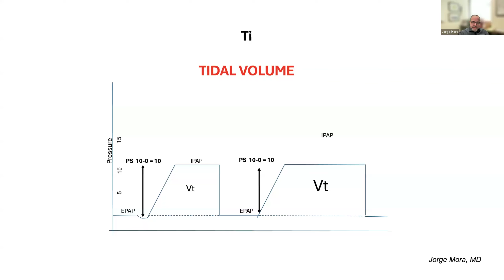Most devices right now, especially ventilators, but it's true for all respiratory assist devices, bilevel PAPs from ResMed, which is probably the most common used component. It's true also for Luna, React Health. It's also true for them. And the important thing I want you to understand is that we're able to define two inspiratory times in these devices. And that's TI min and TI max.